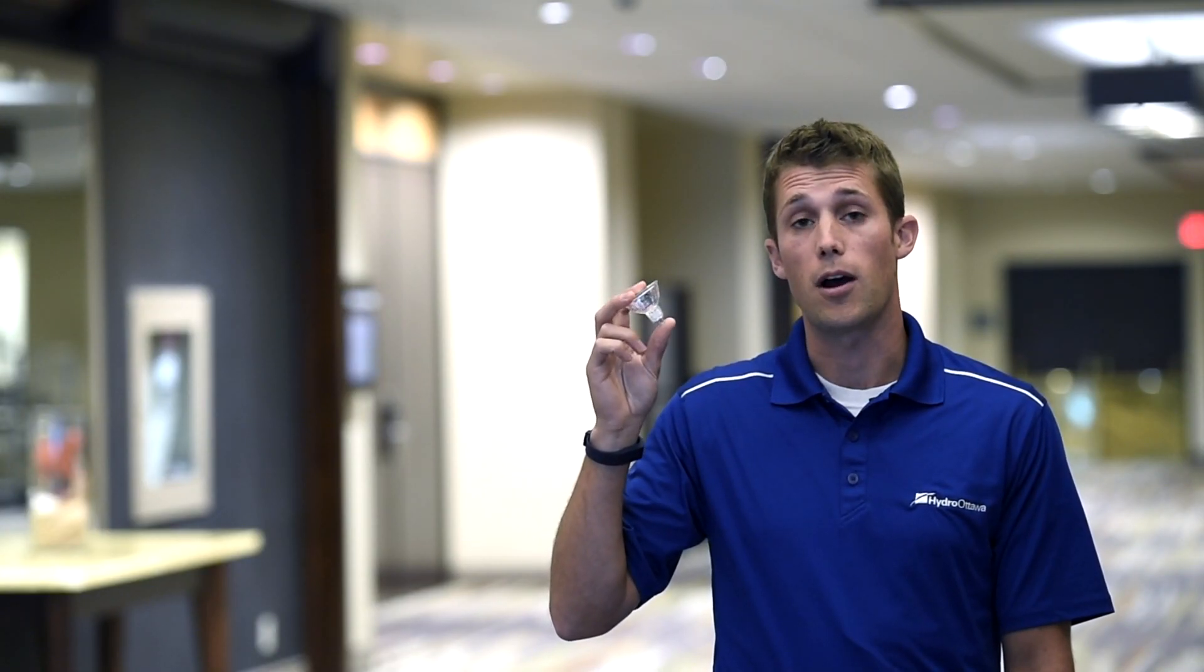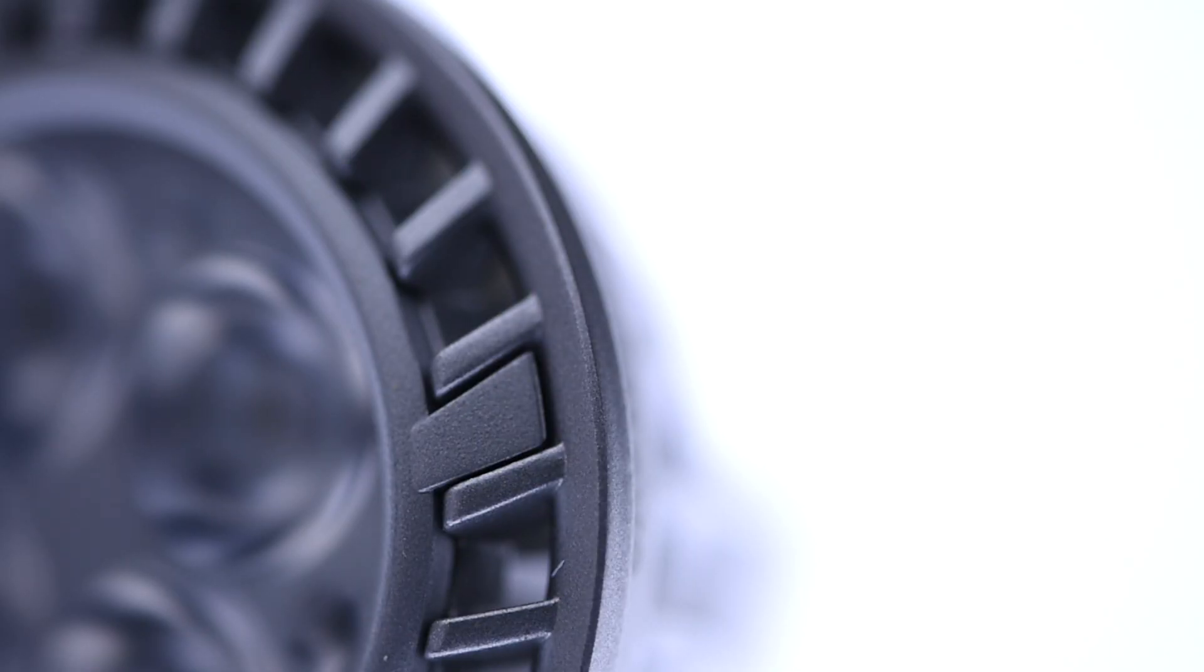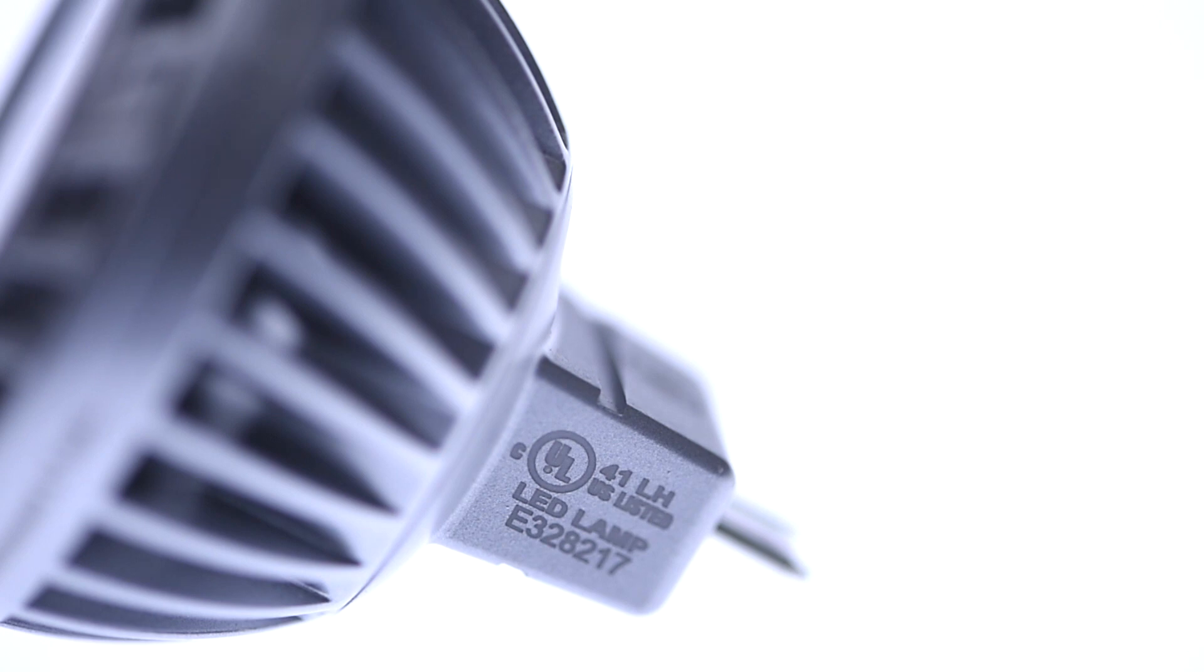MR-16s give off a lot of heat. About 85% of that heat is eliminated when upgrading to LED. LED lights also last 10 to 20 times longer, so building operators can schedule fewer maintenance days.